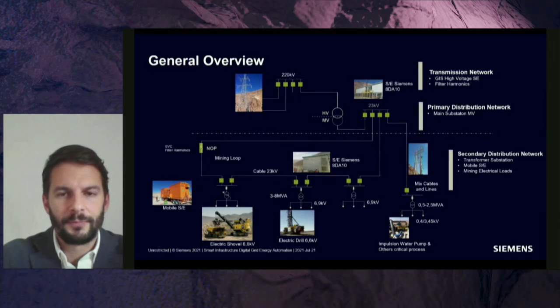Well, if we start here with the picture on the right-hand side, I would start to explain a bit the system architecture we see here. The main principle relates first to the possibility to have in place a so-called decentralized system architecture, where intelligent devices controlling the local breakers can communicate between each other on a peer-to-peer basis without the intervention of a central SCADA. This means that the system can automatically react to an outage or overload event without requiring the intervention of the network or the SCADA operator.